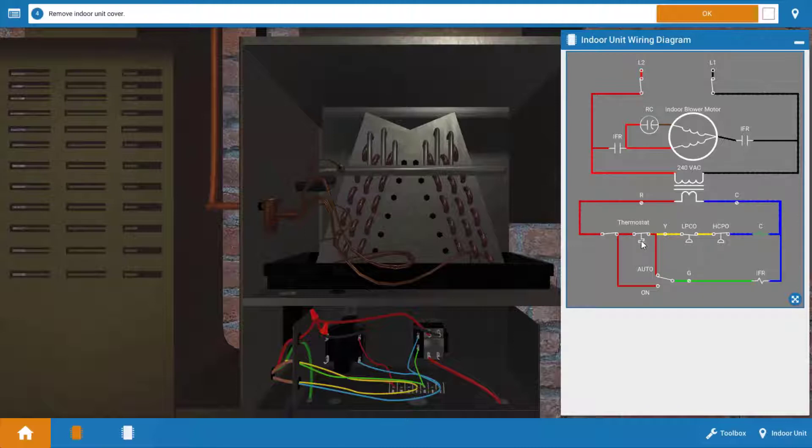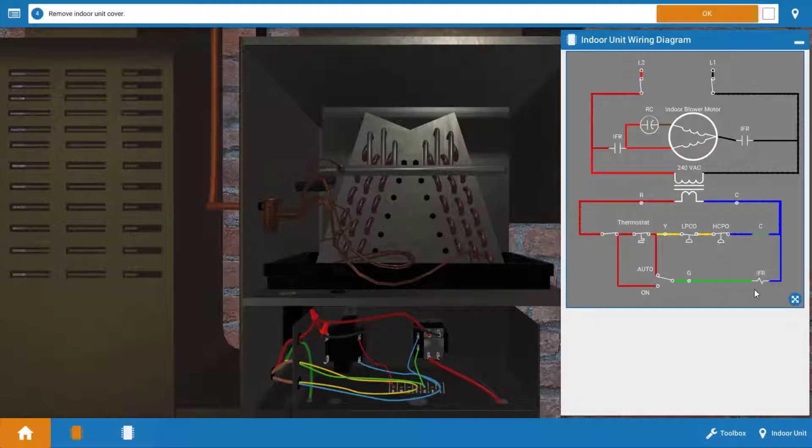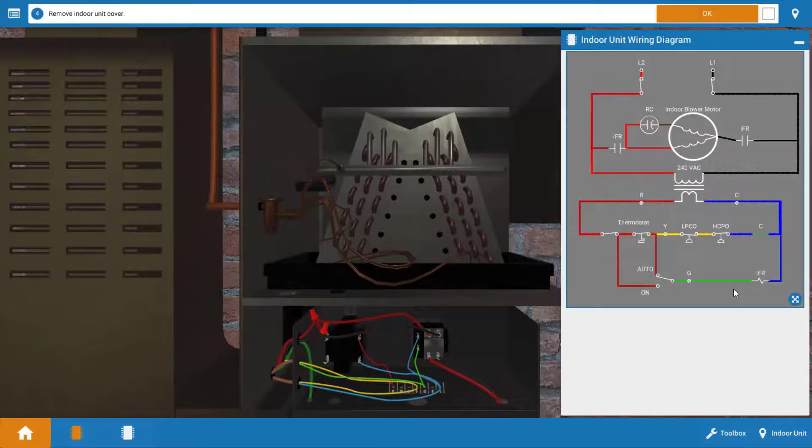Now, even though we know the thermostat contacts are closing because they're powering the contactor coil, it's possible we have a faulty fan switch within the thermostat that's not allowing 24 volts to the indoor fan relay. So again, we've got the indoor blower motor, the run capacitor, the indoor fan relay, or the thermostat. That's it for possible causes. Let's find out which one it is.